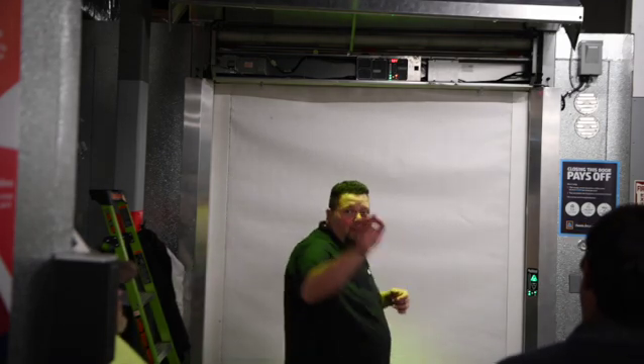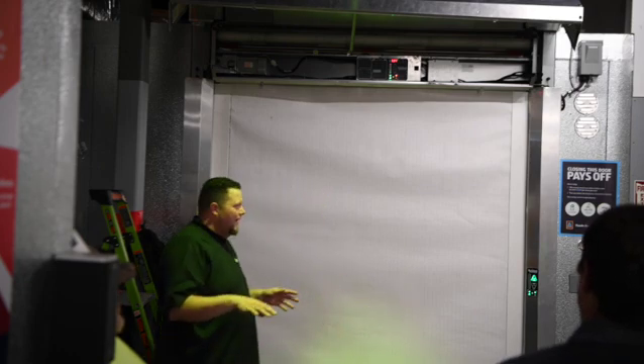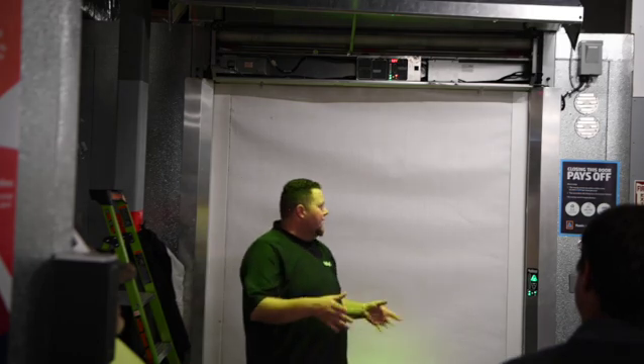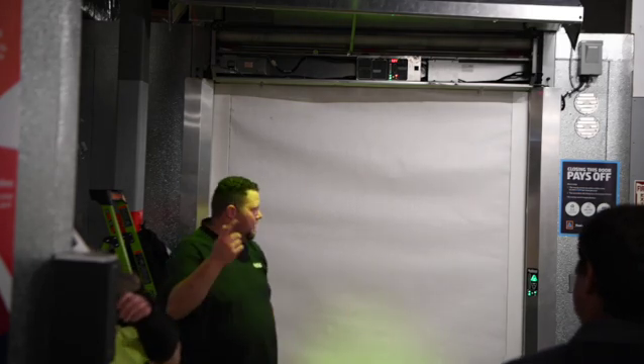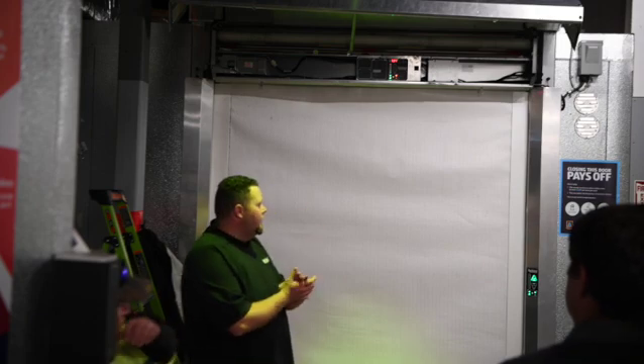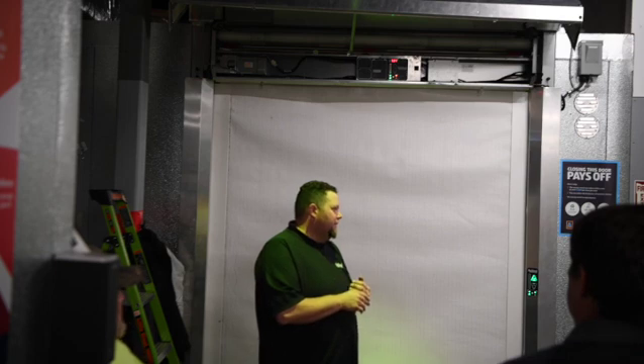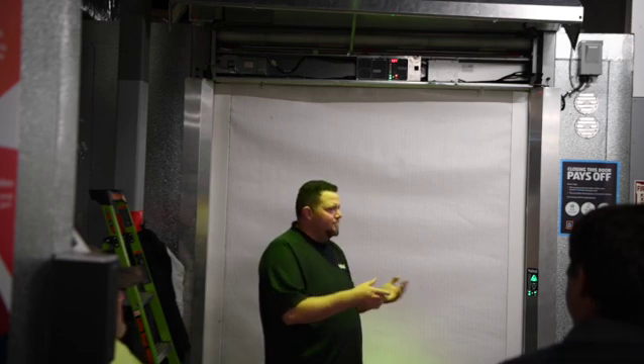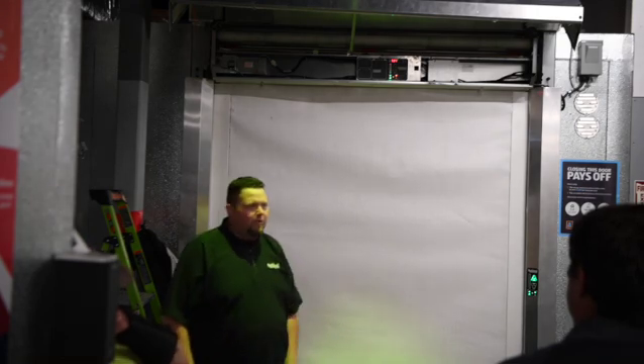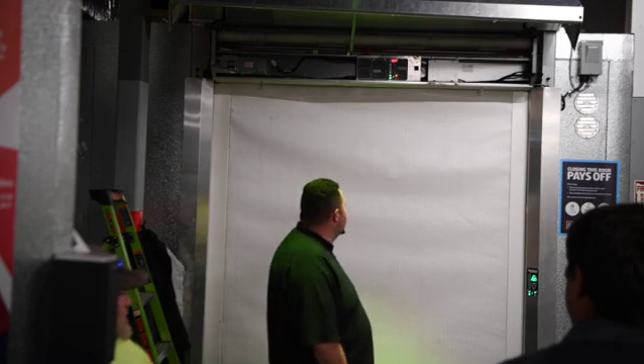So I think that one over there has some tape on it. Don't ever worry about taping it. You can shut it off right there at that controller if it's giving you an issue with the traffic or whatever the reason may be. You can just shut it off with that controller. You don't have to throw tape on it. Because the bad thing about throwing tape is eventually tape falls off, and then you're getting a nuisance call, and you're like, well, we ain't had this before. It looks like something different, but you know, tape fell off or something.